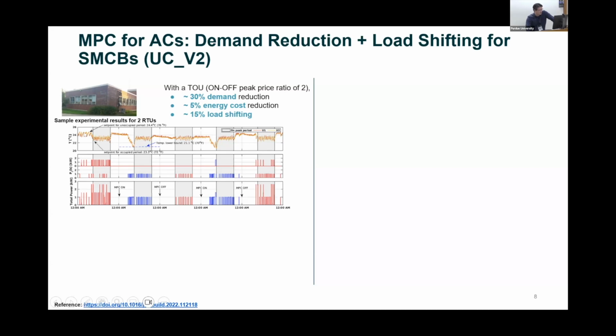And the temperature drops because the occupied period starts and the set point is lowered, and you can see all the RTUs activated at the same time. But on the next day, obviously the conventional thermostat control doesn't care about the grid signals because there's no mechanism for it to react. But model predictive control tries to pre-cool the spaces by adjusting the set point.